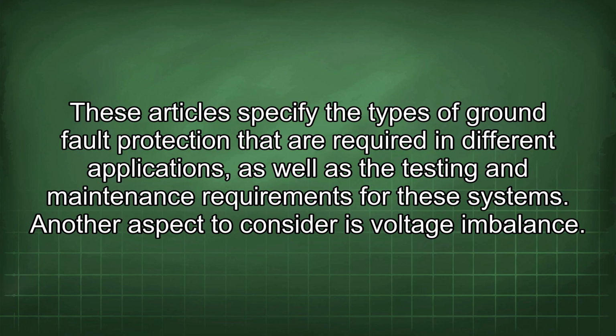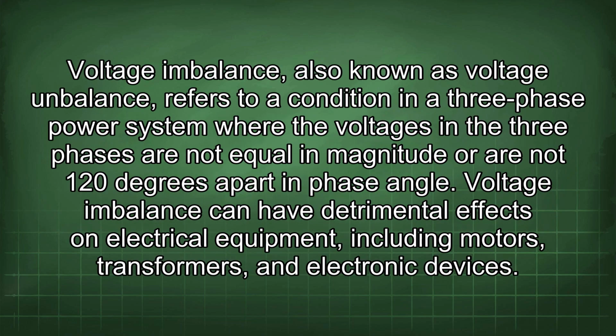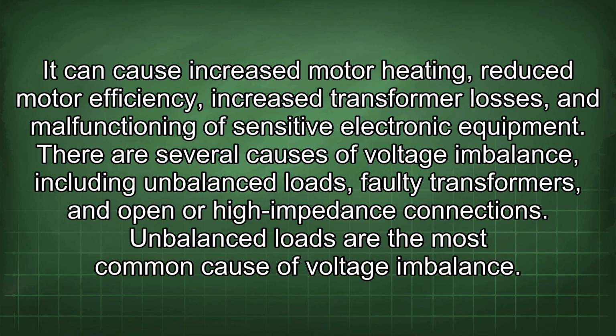Another aspect to consider is voltage imbalance. Voltage imbalance, also known as voltage unbalance, refers to a condition in a three-phase power system where the voltages in the three phases are not equal in magnitude or are not 120 degrees apart in phase angle. Voltage imbalance can have detrimental effects on electrical equipment, including motors, transformers, and electronic devices. It can cause increased motor heating, reduced motor efficiency, increased transformer losses, and malfunctioning of sensitive electronic equipment.